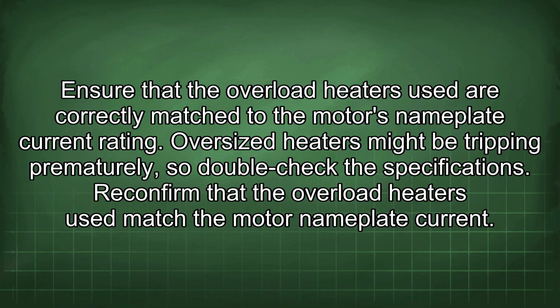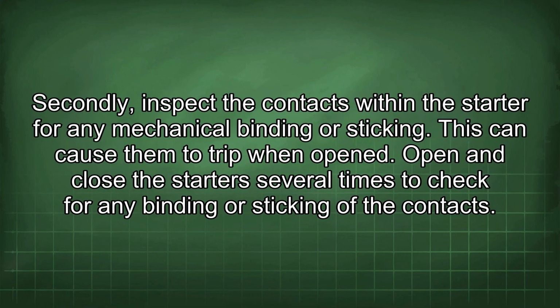Oversized heaters might be tripping prematurely, so double-check the specifications. Reconfirm that the overload heaters used match the motor nameplate current. Secondly, inspect the contacts within the starter for any mechanical binding or sticking. This can cause them to trip when opened. Open and close the starters several times to check for any binding or sticking of the contacts.